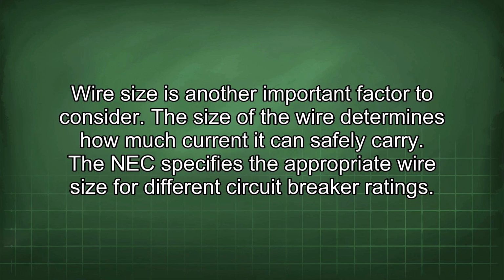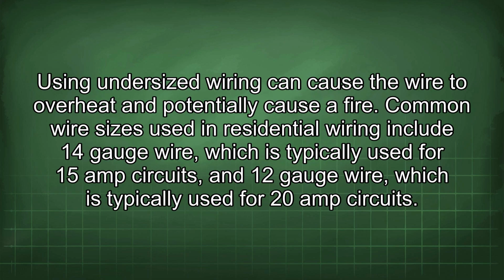Wire size is another important factor to consider. The size of the wire determines how much current it can safely carry. The NEC specifies the appropriate wire size for different circuit breaker ratings. Using undersized wiring can cause the wire to overheat and potentially cause a fire. Common wire sizes used in residential wiring include 14-gauge wire, which is typically used for 15-amp circuits, and 12-gauge wire, which is typically used for 20-amp circuits.